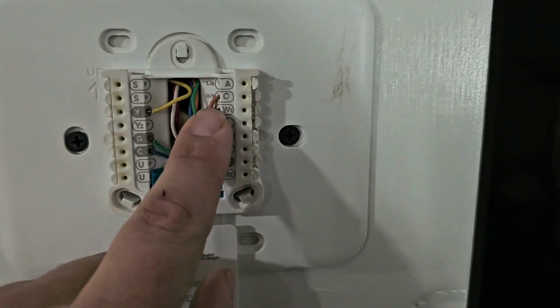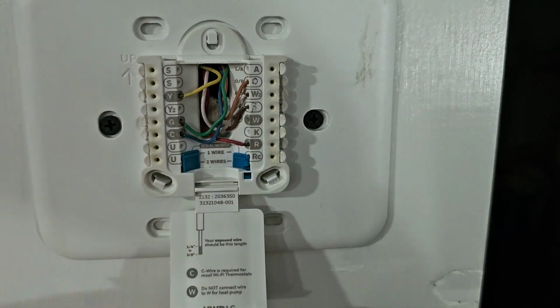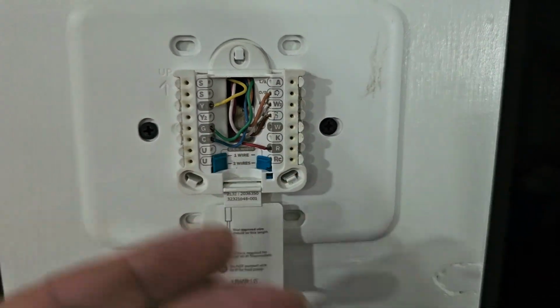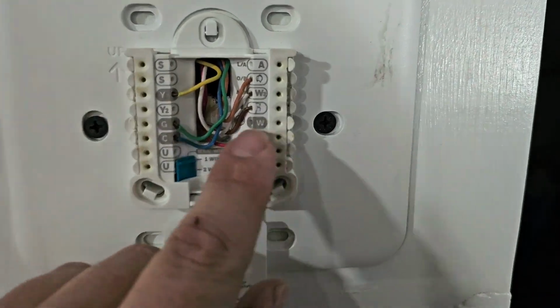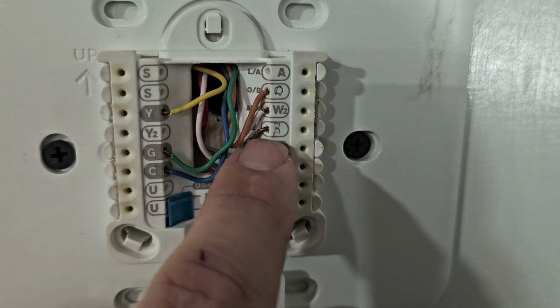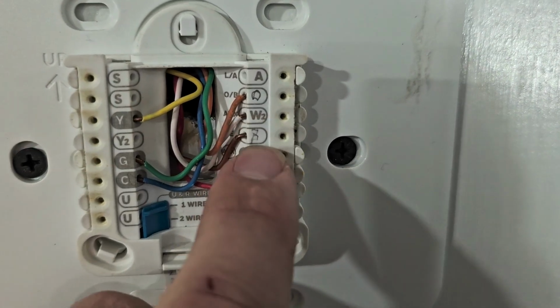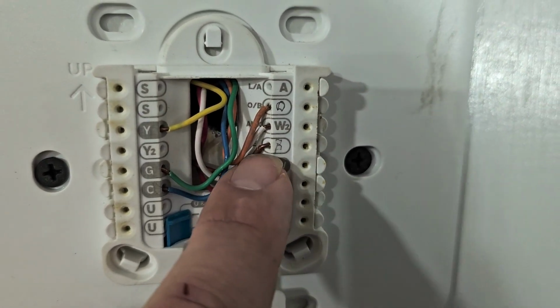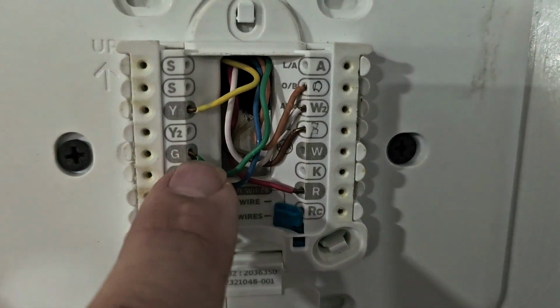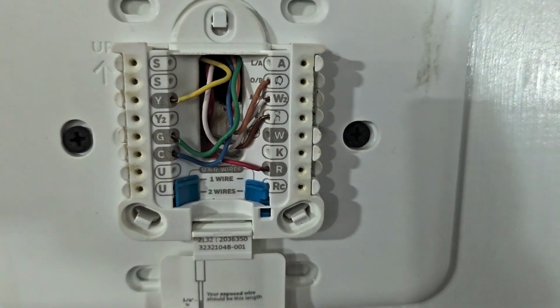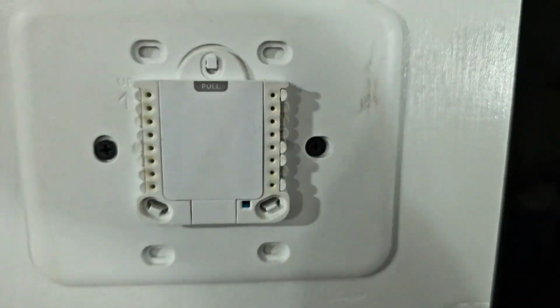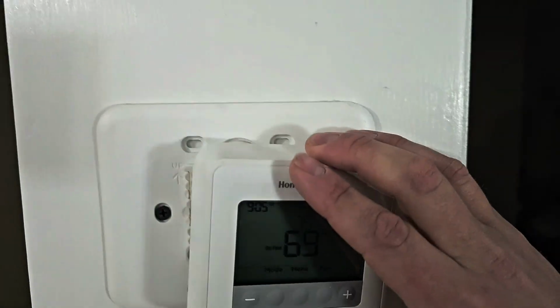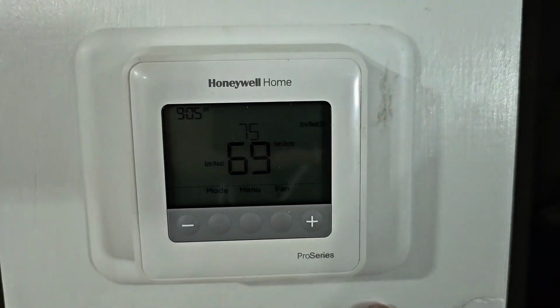The aux terminal is energized whenever you're in the regular heat mode, and that is to supplement your heat pump to heat your home. Whenever it's in emergency heat, this thermostat will engage the E terminal, which is just gonna turn your heat strips on, the G terminal, which is gonna turn your fan on, and that's how you have emergency heat. So now that we know it's hooked up in the thermostat, we need to make sure it's actually hooked up in the unit.